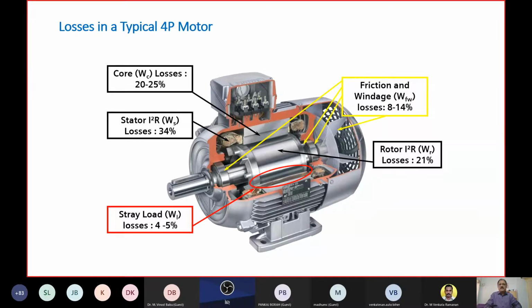Iron, friction and windage losses are sometimes called no load losses. So no load tests will reveal the total iron, friction and windage losses. If you look at the stray losses, I have put this under the red box. Primarily, the objective is to discuss what has happened with the new IE rule to the stray load loss measurements.